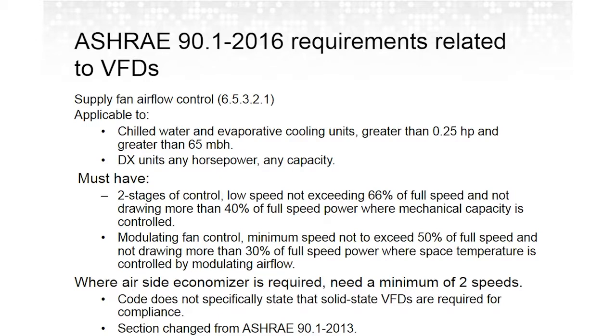But rather than dive too deep into that, let's look at the basic requirements. What we're seeing is a requirement for multi-speed control, not fully modulating control, the type of control that we associate with VFDs. You can accomplish the multi-speed control requirements with a number of different methodologies. However, under certain size systems, in addition to multi-speed control, you're also required to have a certain level of efficiency of that particular system when it's operating at the reduced speed.